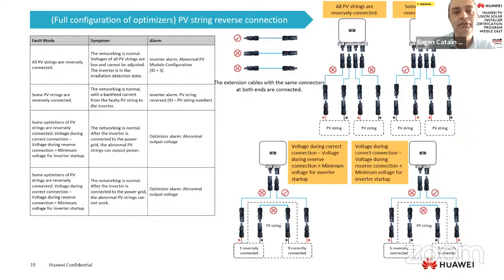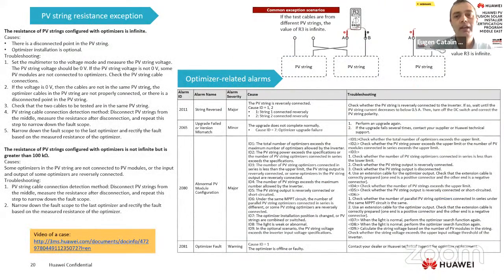If you do a wrong installation, a wrong string connection, of course the inverter will generate an alarm: all PV strings reverse, some PV strings are reverse connected, some optimizers of the PV string are reverse connected, and so on. According to the alarm, you will act and fix the problem. Also, the optimizer will generate some alarms, such as optimizer fault, abnormal PV module configuration, and so on. If you check on the inverter, or on the website, you will also find a troubleshooting guide. You can act if you read exactly what the troubleshooting recommendations are, and what you need to check.